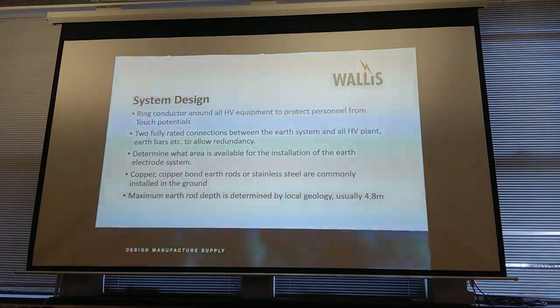And unfortunately, historically, earthing has been one of those things that's been left right to the last minute. And then you have to start getting drill rigs in and things like that, because if you can't go out, you've got to go down. If you start to think about these things a little bit earlier on, sometimes, especially when a building is being cast or is coming out of the ground, you can start using piles. You can put earth rods through the slab and put earth rod seals on. There are many different ways of doing it, but it just needs a little bit of planning. If that ground floor has already been cast, then I'm afraid it's a little bit late, but that's one point.